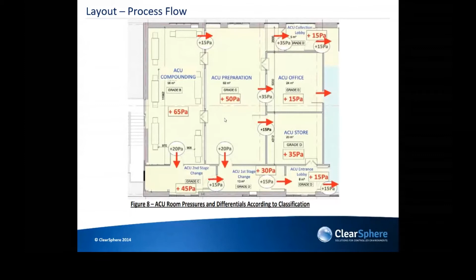Coming from outside, you have a differential pressure of plus 15 pascals going into the entrance lobby, and it cascades up from there: another plus 15 pascals into the first stage change, again 15 pascals into the second stage, and 20 more. So you end up with a total of 65 pascals differential to atmosphere, or your reference point, which was just outside the pharmacy here. That was primarily our starting point for design.